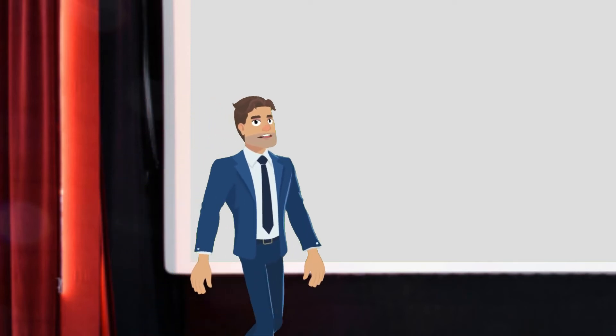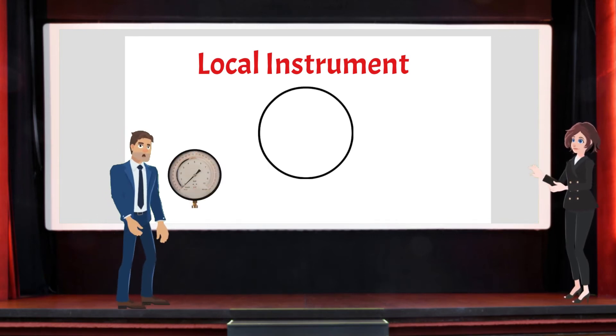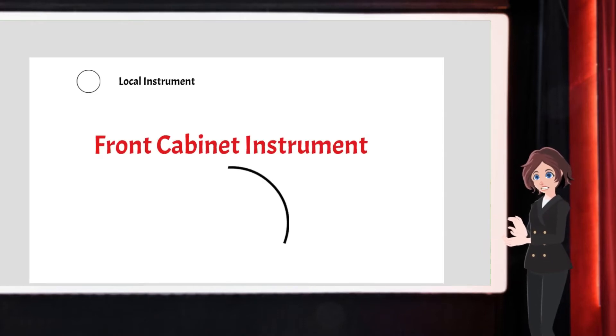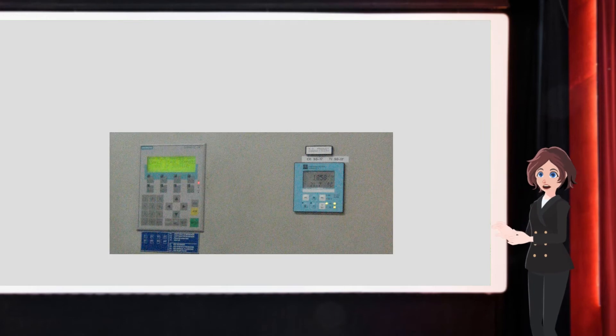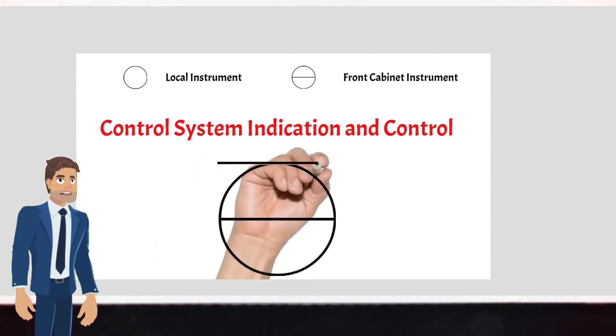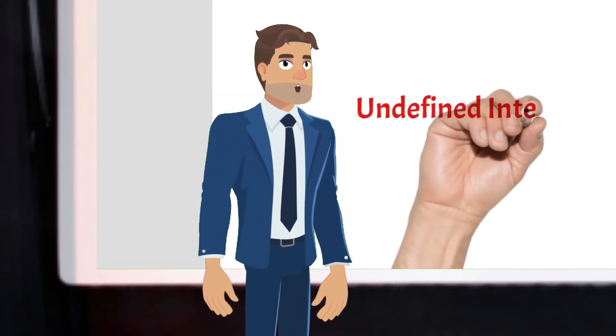How can instruments be identified on the P&ID? There are multiple graphic symbols related to instrumentation; in this video we will analyze the four main symbols. First, the local instrument, represented by a circle — all instruments installed in the field are local instruments, for example a pressure gauge, a temperature indicator, or any kind of transmitter. Second, the control cabinet instrument on front, represented by a circle divided in two by a continuous horizontal line; if the line is dashed, the instrument is installed inside the cabinet. Third, the monitor or HMI control panel indication (software indication), represented by a circle inscribed in a square divided by a horizontal continuous line. Fourth, the indefinite interlock, represented by a square rotated 45 degrees.